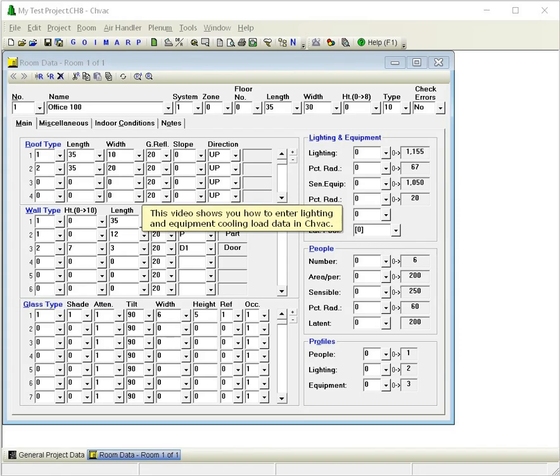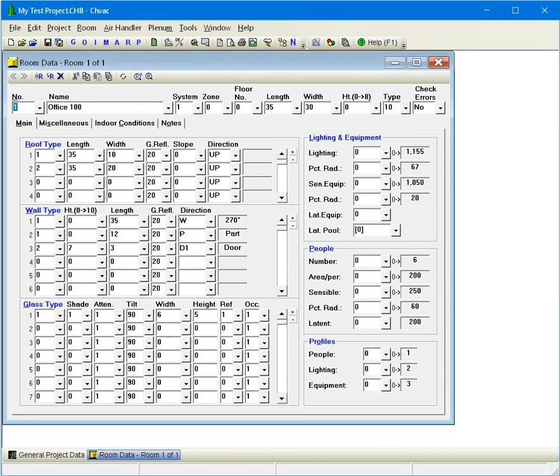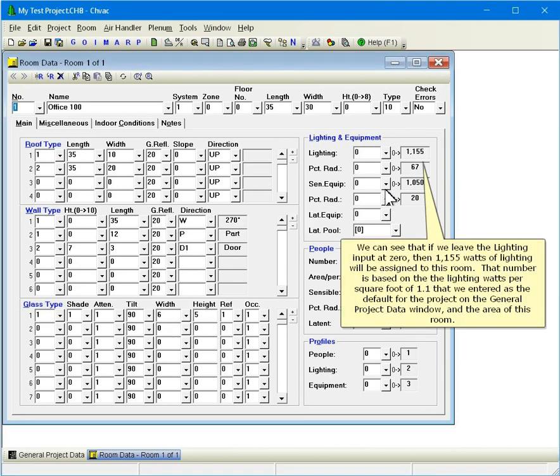This video shows you how to enter lighting and equipment cooling load data in CHVAC. If we leave the lighting input at zero, then 1155 watts of lighting will be assigned to this room. That number is based on the lighting watts per square foot of 1.1 that we entered as the default for the project on the general project data window and the area of this room.